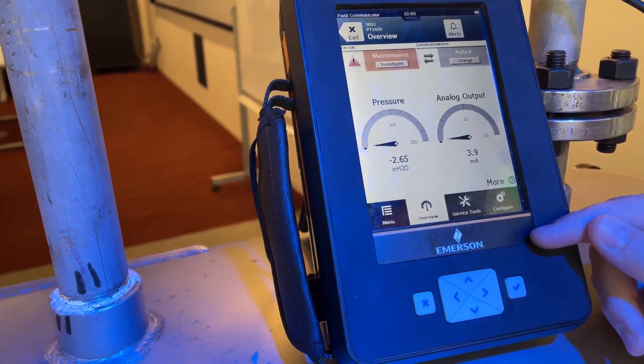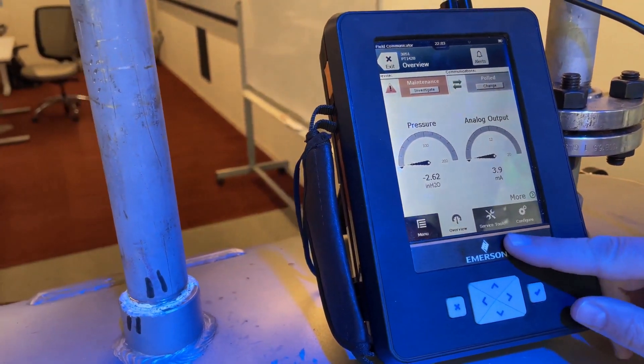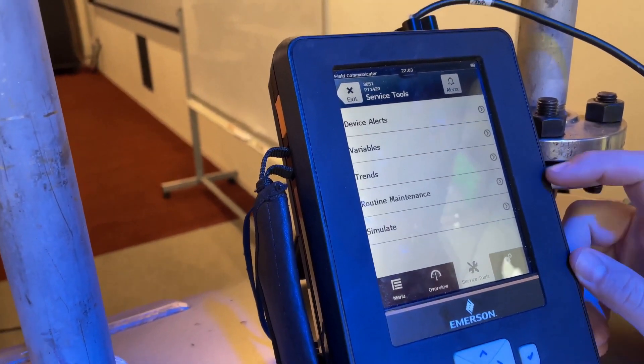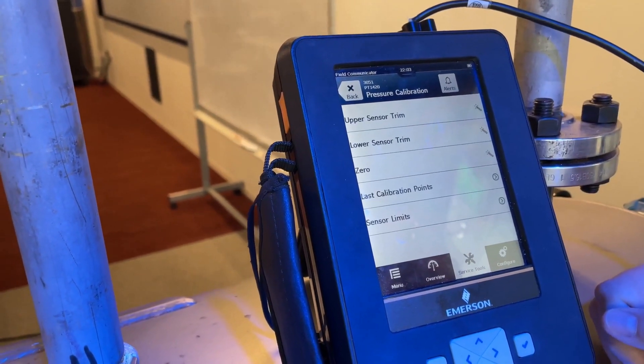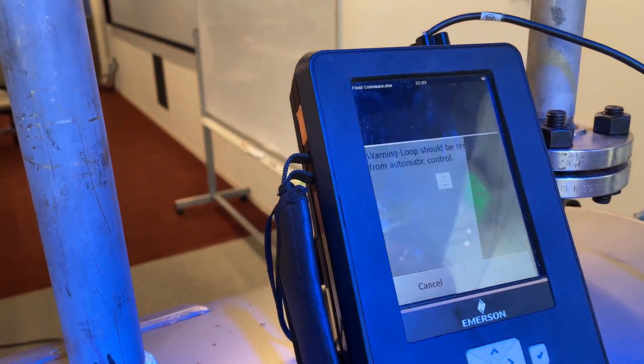So to get rid of this mounting pressure effect, we're going to perform a zero trim by going to the service tools tab, going to routine maintenance, pressure calibration, performing a zero trim.